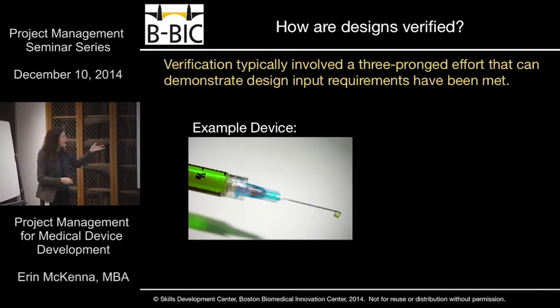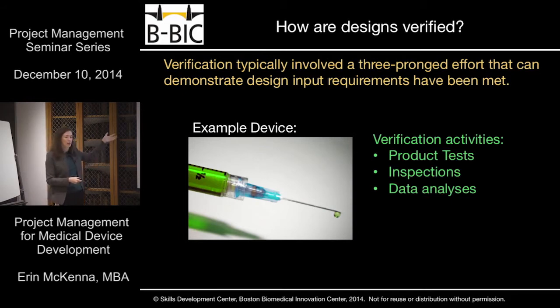For this device, you're going to be doing product builds, and you're going to be measuring the products in a variety of ways that you'd already identified when you developed your outputs. In some cases, you'll be doing things that look more like qualitative inspection versus quantitative measurement, where you can't do quantitative measurements. You'll be doing a lot of data analyses to ensure that things are within confidence ranges that you've determined would be acceptable from a control standpoint, dependent on the criticality of each of those design elements. So that's the design verification.